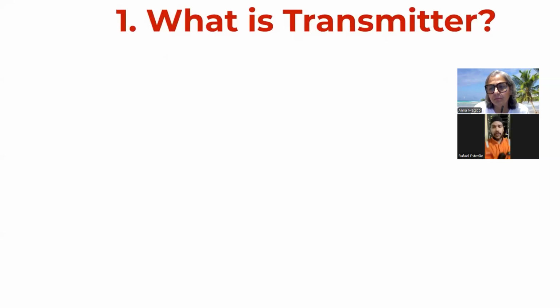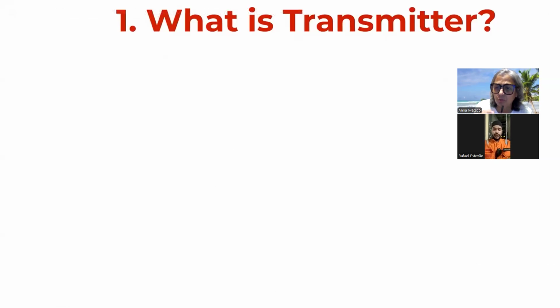Every day I have maintenance, corrective maintenance and preventive maintenance, because this value needs to be real for the control room - this value needs to be true. For example, on the screen, if the pressure transmitter gives the value 10 bar, this value needs to be correct. I need to be sure this value is correct because I need to calibrate and certify the instrument, the transmitter.